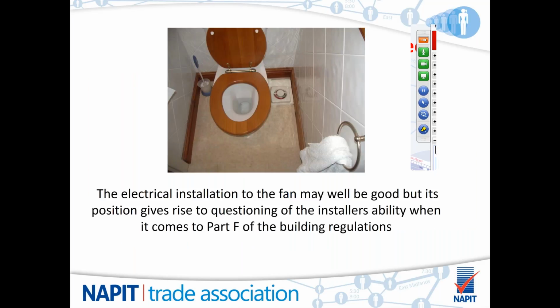Other pictures that members send in sometimes can be rather amusing. The fan being installed on the floor really may be a very, very well installed electrically. What does come into mind here is that whoever did install that fan really hasn't got much idea when it comes to Part F of the building regulations and how ventilation works. So again, although Part F is not under the periodic inspection regime, so to speak, it would certainly, in my mind, need bringing to the customer's attention that this is not an adequate way of ventilating a toilet.